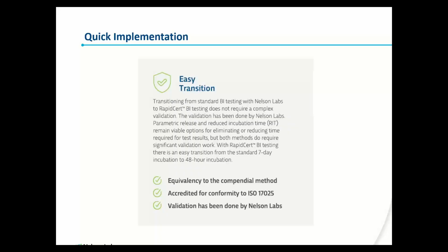And for this test, we are able to have quick implementation and an easy transition from either a standard BI or an SCBI into using this RapidCert process. Because we've already done the validation approach, that is completed, and there's no additional validation work that would be required in order to start moving to the use of this RapidCert approach.